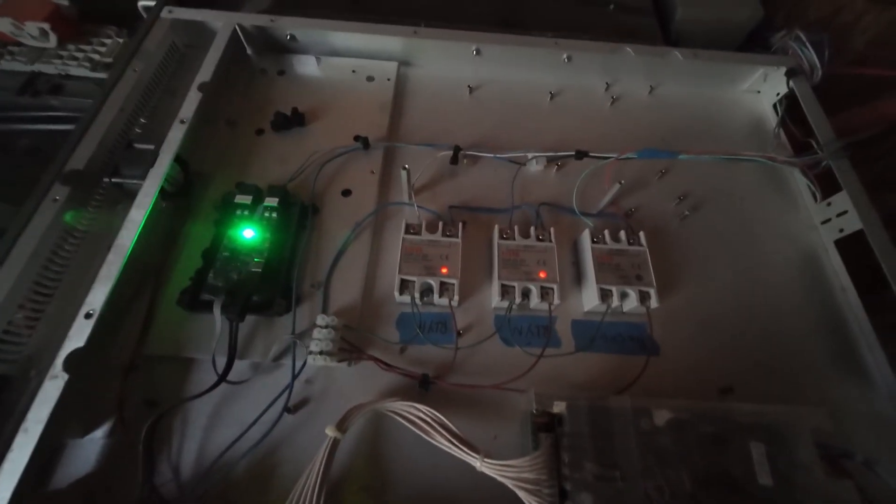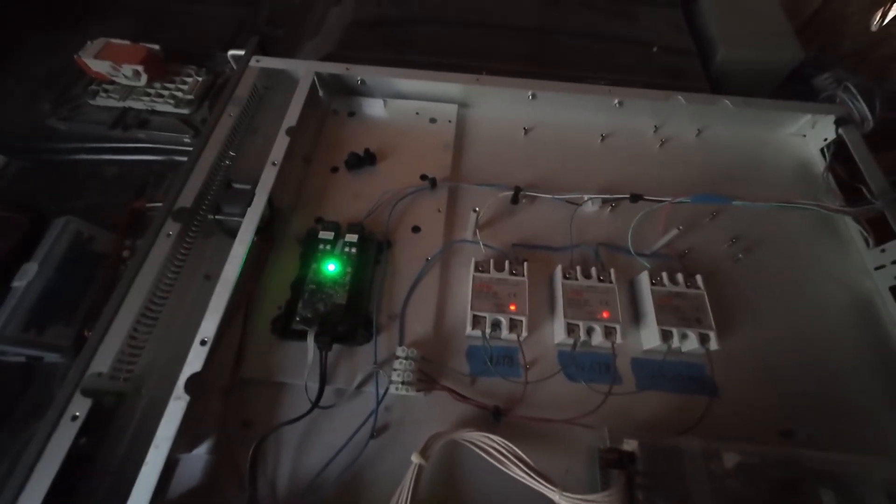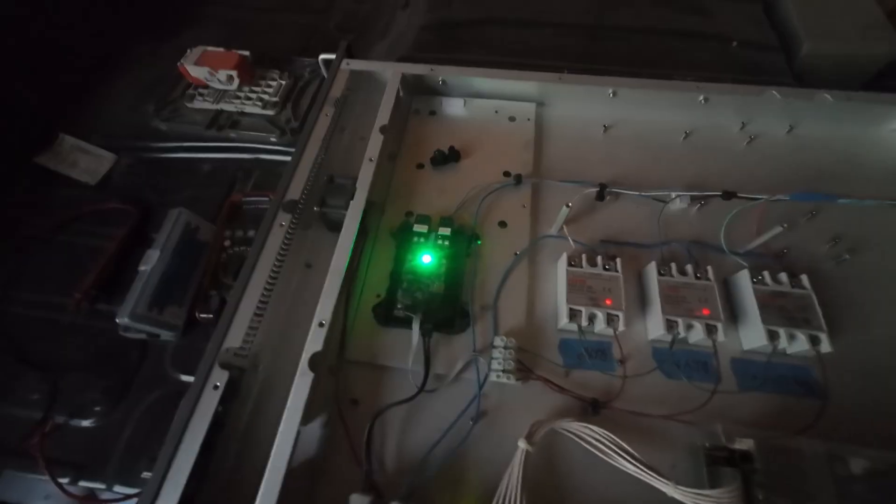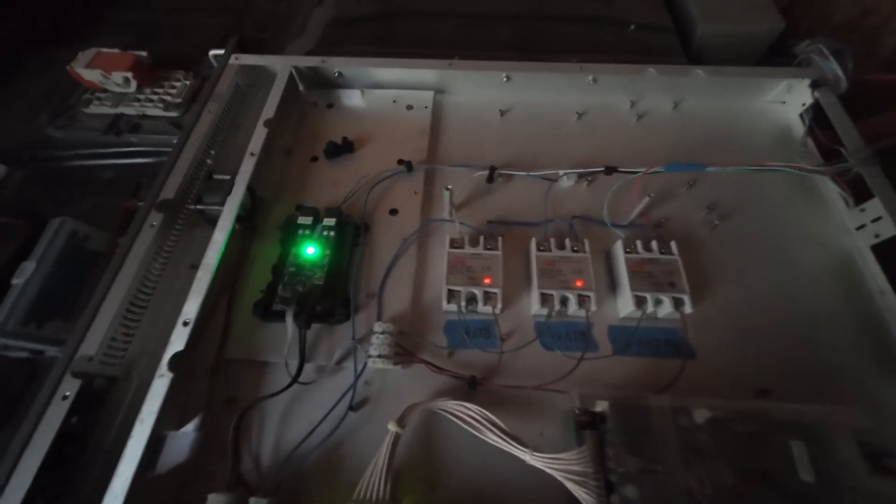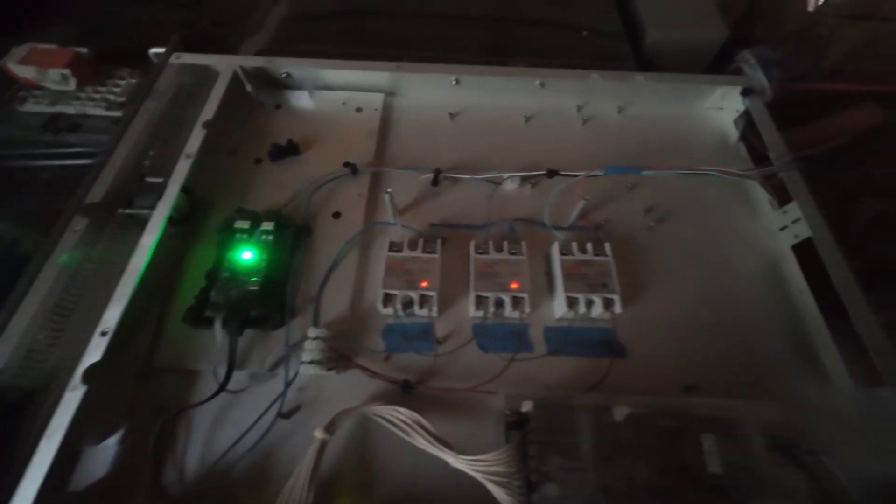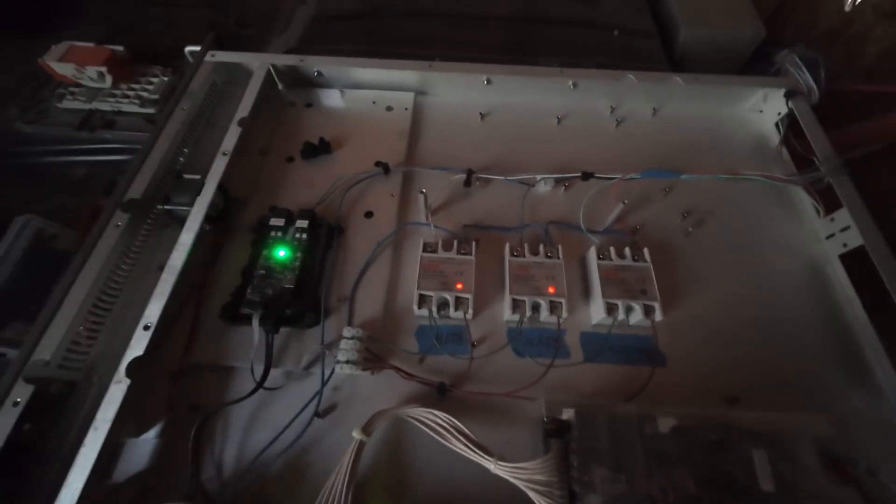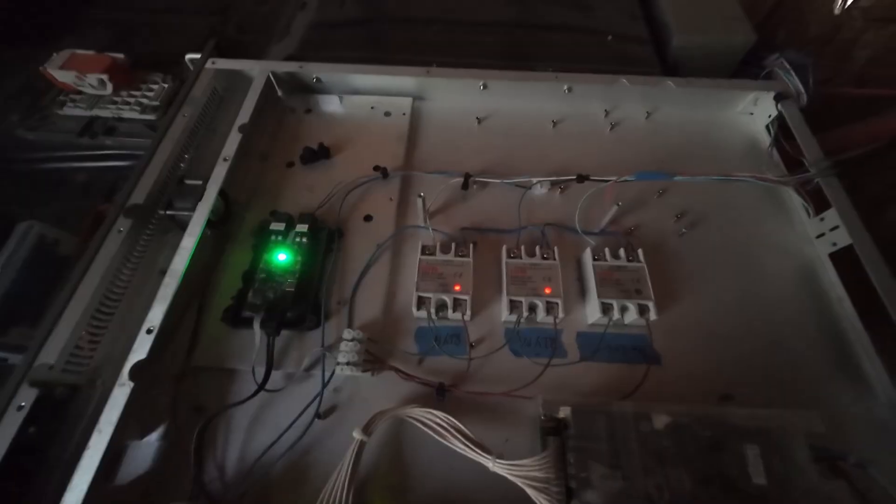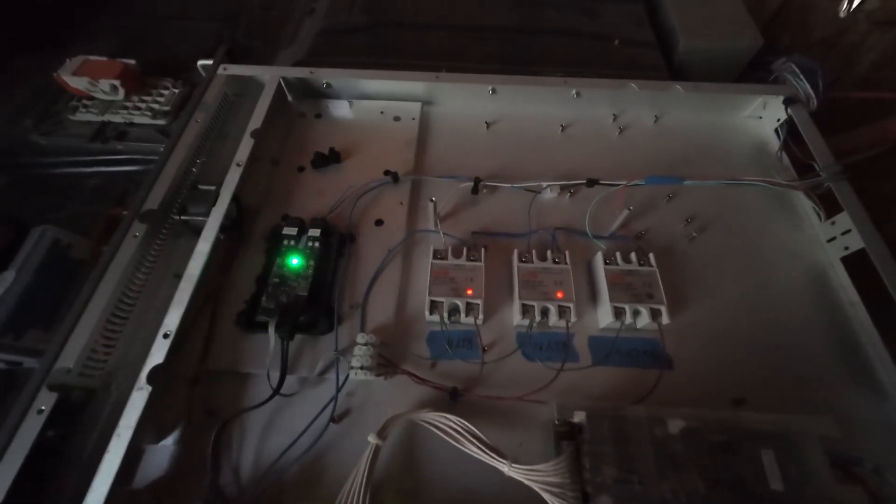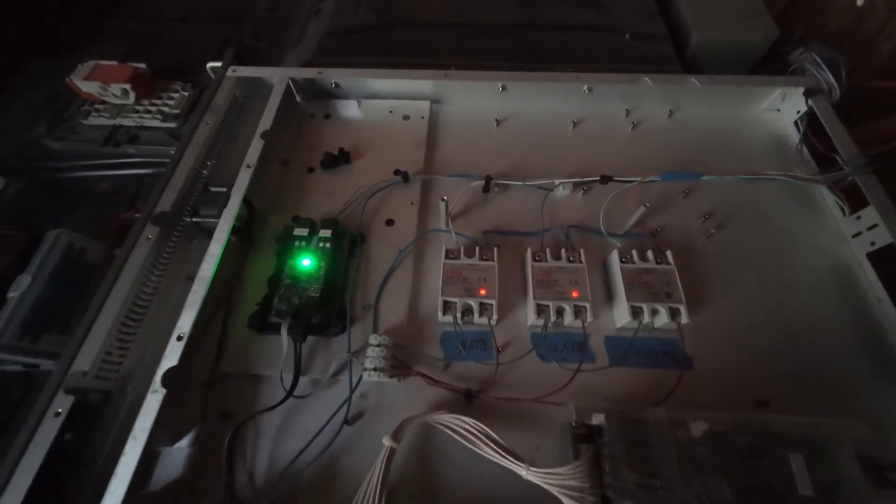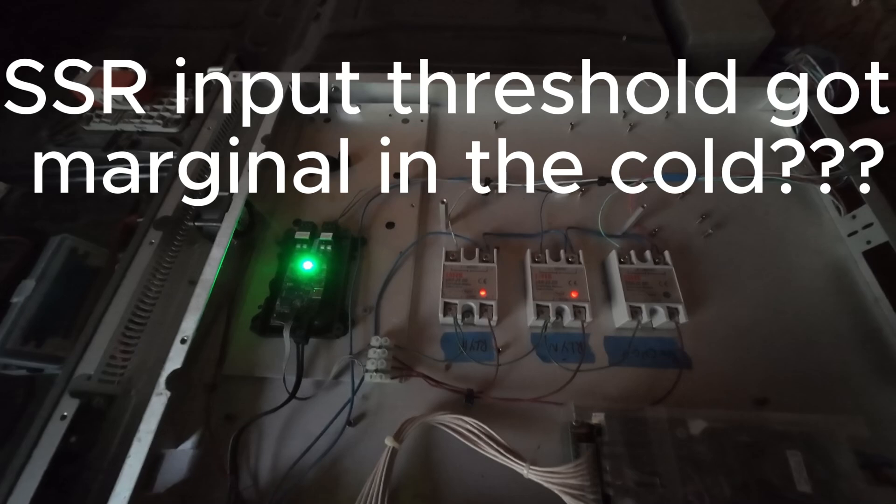What I found was when I turned the power back on to the controller, the SSRs didn't come on until I started probing around on the control voltage terminals. I've repeated that several times and it's doing the same thing.